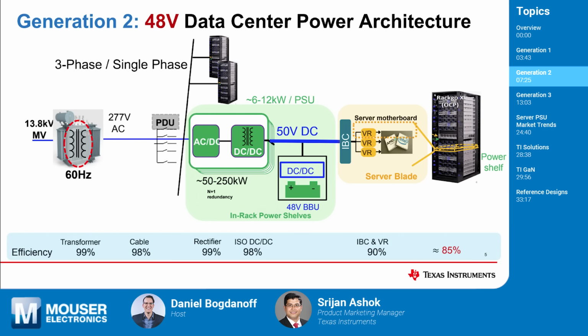Great question, and it segues right into how designers are now thinking about efficiency and power density. 12 to 48 volt, very simply, is 4 times the voltage level. To deliver the same power, you need 4 times lesser current, because power is nothing but V into I. So the moment you go to 48 volts, your I-square-R losses go down - because current has gone down by 4 times, I-square can theoretically go down for the same power level by 16 times, since it's 1 by 4 squared. That's the first major advantage.